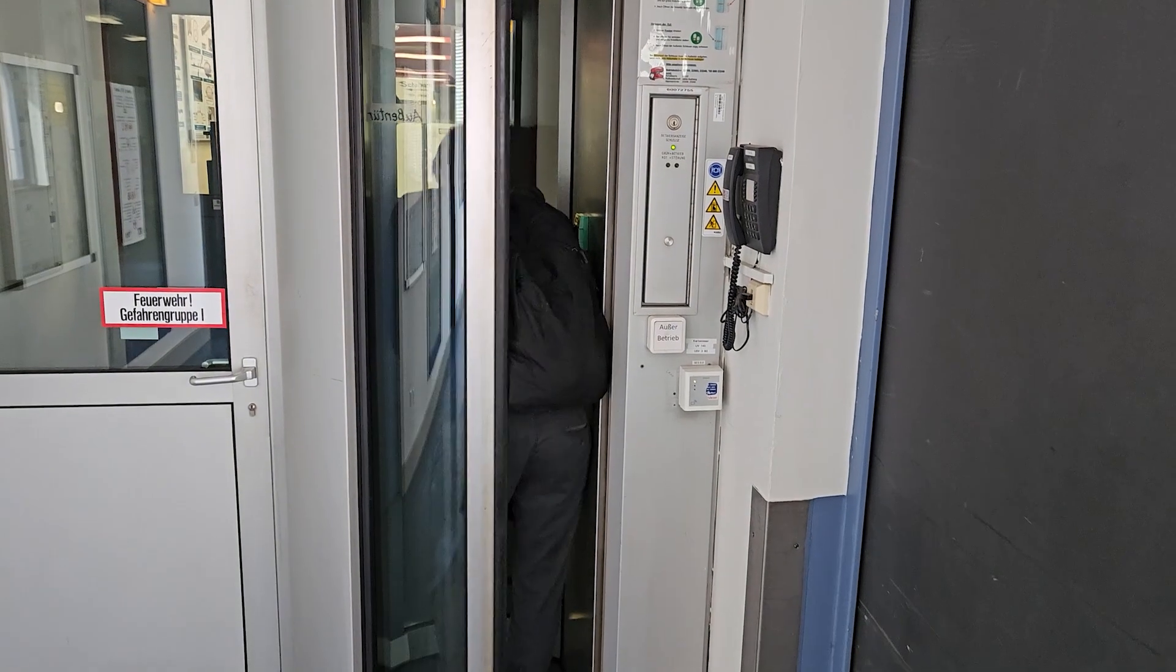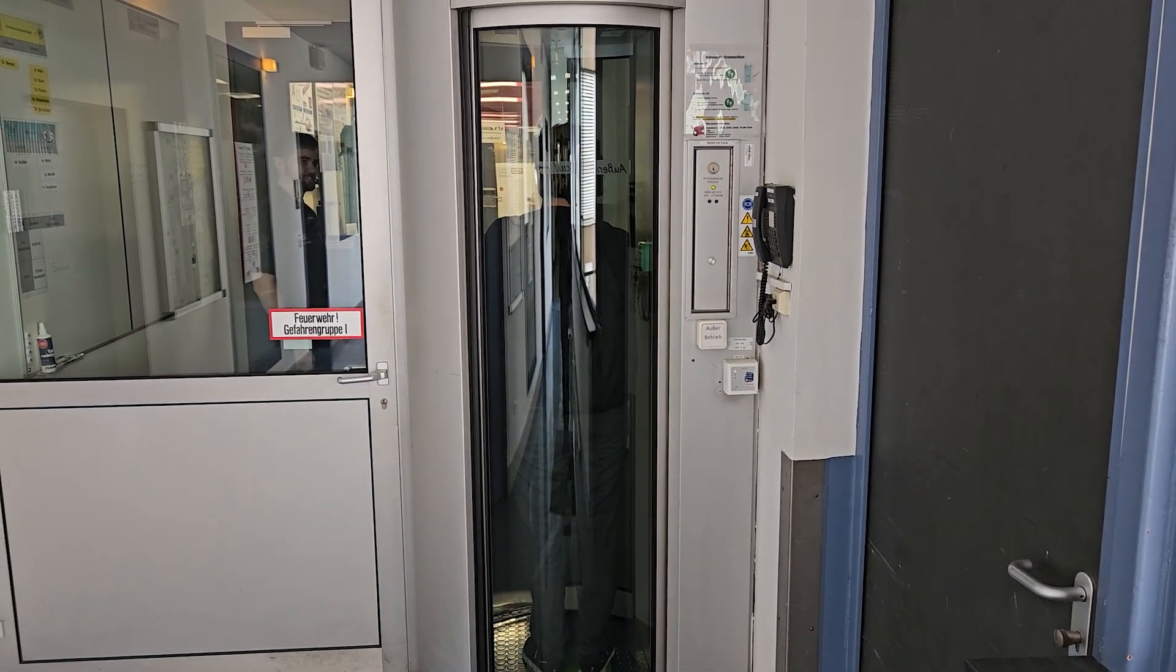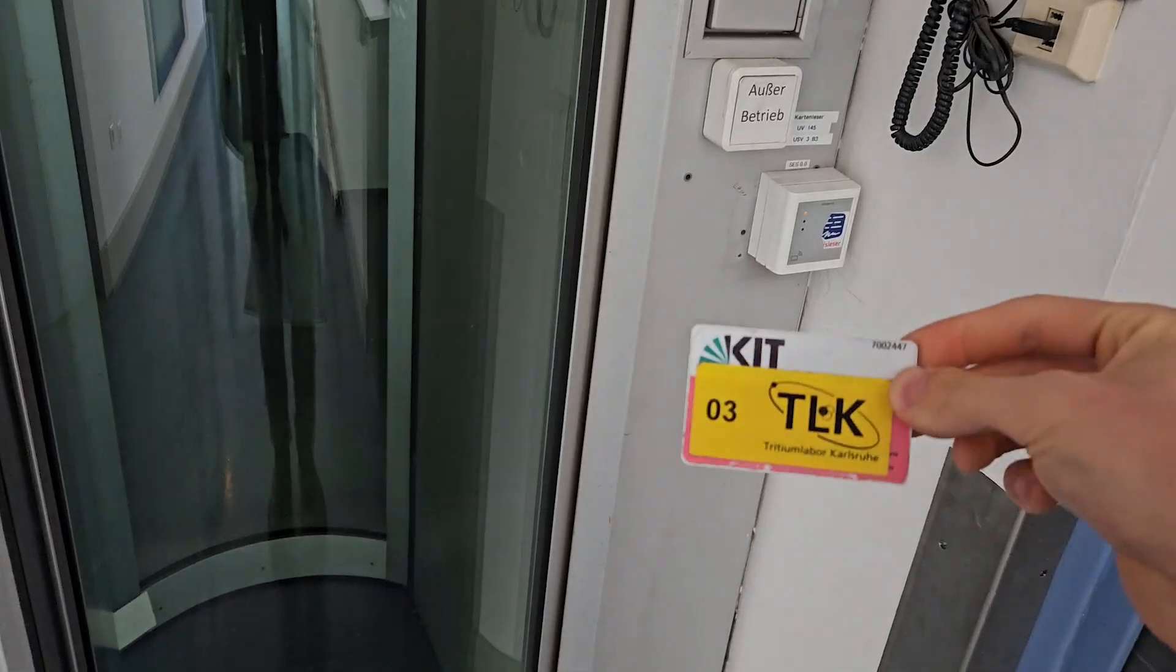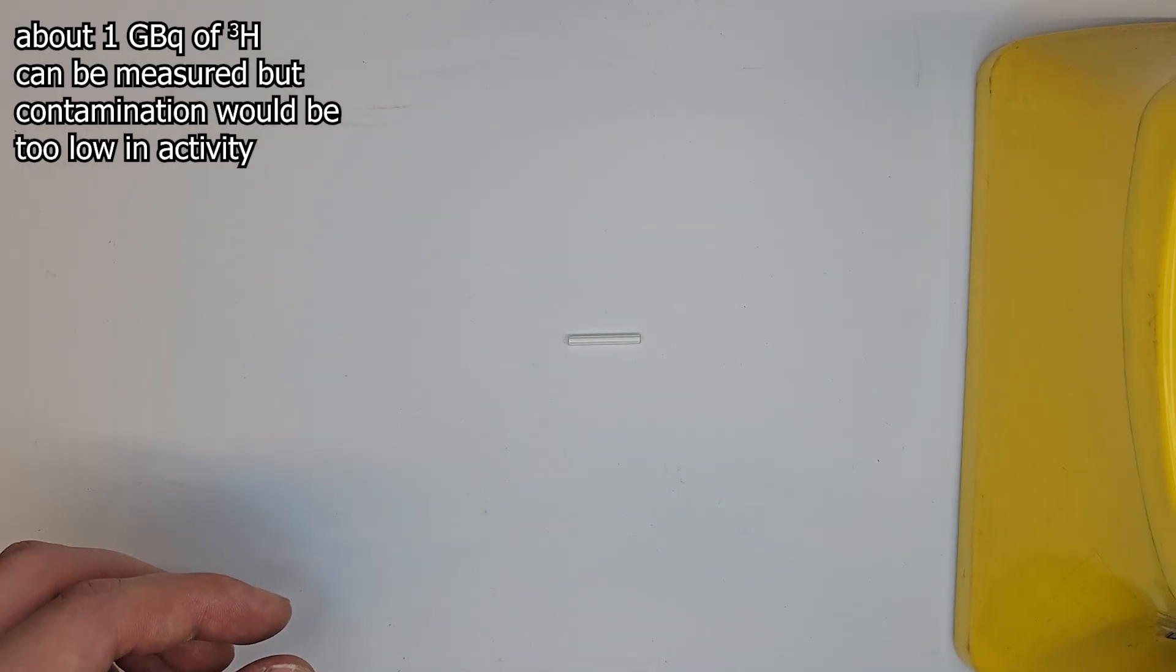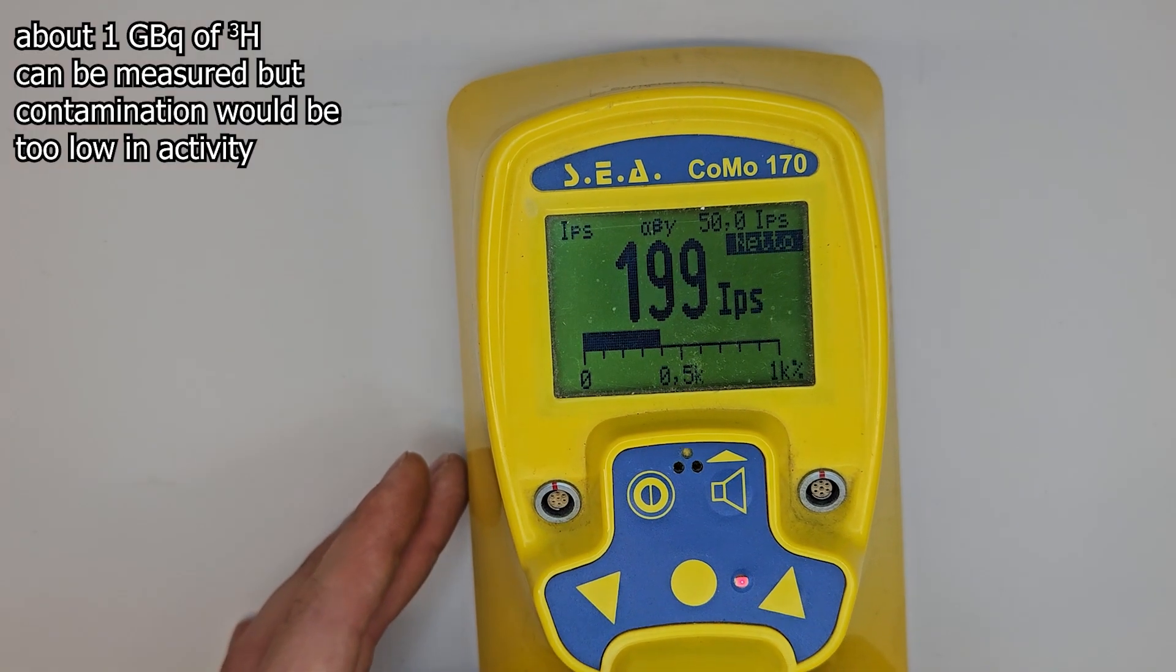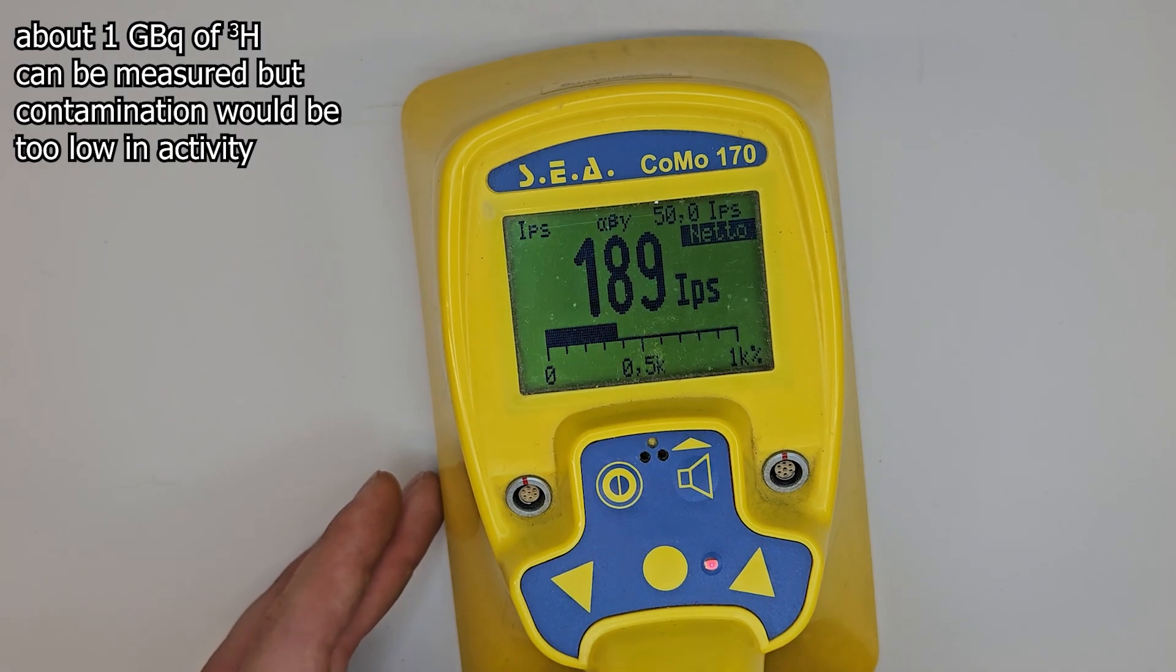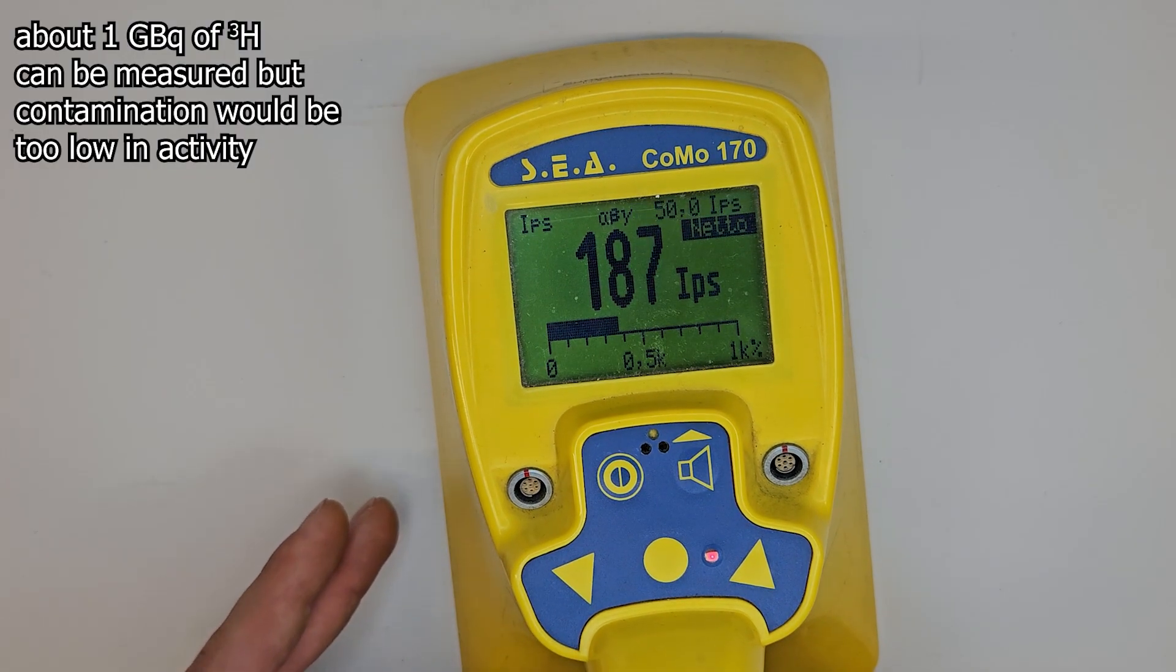So you go through an airlock into the laboratory, which, like all nuclear laboratories, is under negative pressure, so that nothing can go out. But you don't wear a film badge or an electronic personal dosimeter. They wouldn't react to the tritium radiation at all. There's also no such thing as a classical contamination monitor, as they also do not react to tritium radiation. Of course, there's a bit of Bremsstrahlung, but it's not worth mentioning.